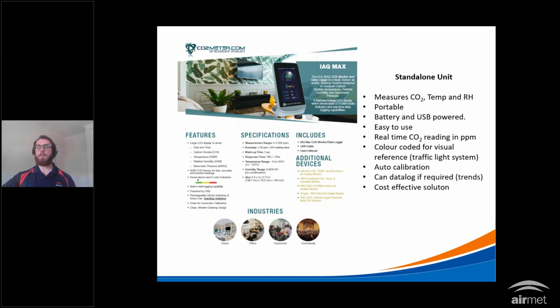Some features of the IAQ Max are as follows: it measures CO2, temperature and humidity, and supports a rechargeable battery. The battery will support a maximum of 3 hours operation while disconnected from a power source. It may be powered simply via USB, a wall socket, or laptop connection. It provides a colour display, including a user-friendly traffic light system indicating current air quality - green good, red bad. It provides data logging functions at an interval ranging from 1 to 60 minutes. The data logger may only store a maximum of 30 days of data, at which point it will begin overriding the earliest data point. It also provides a simple method for recalibration, either automatic or manual.